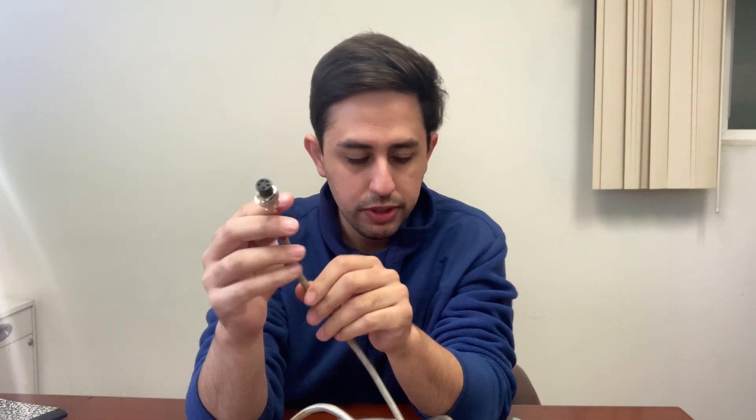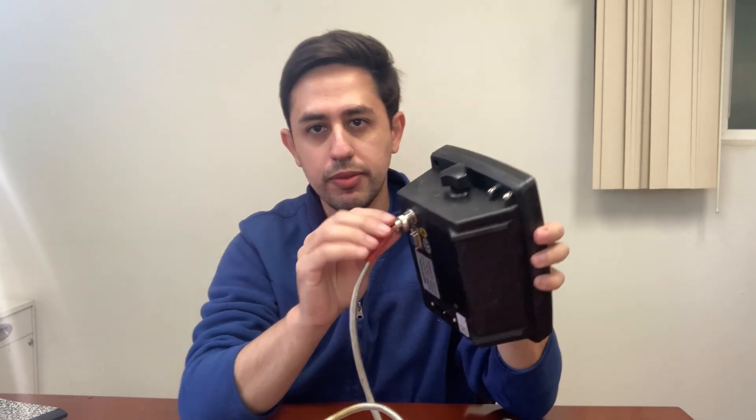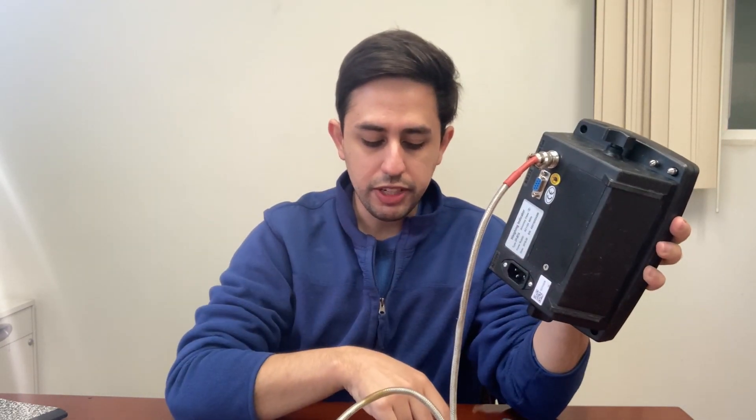Hello, this is how to fix error six on the OP901. The first thing you will do is check your five pin home run cable. This is the connector cable that goes from the back of your 901 to the base.